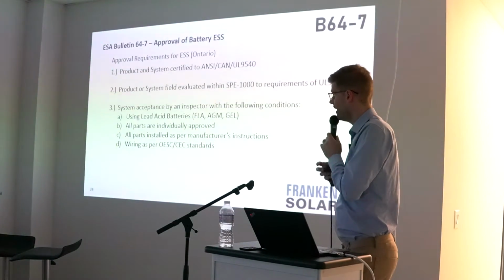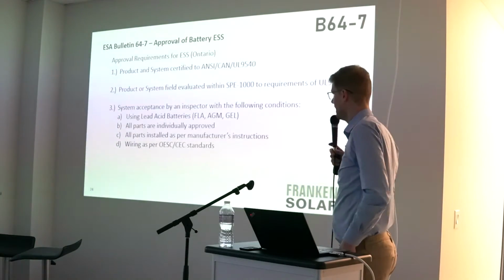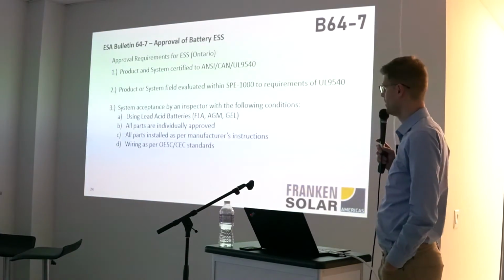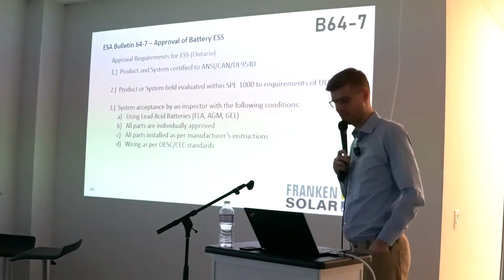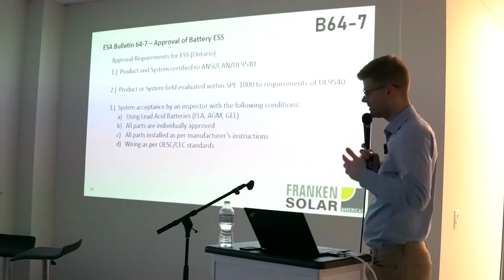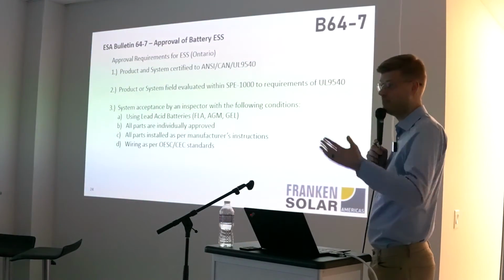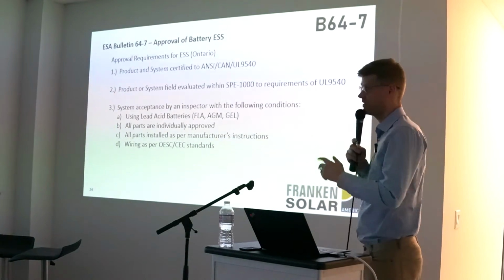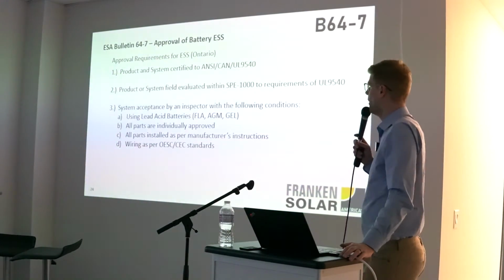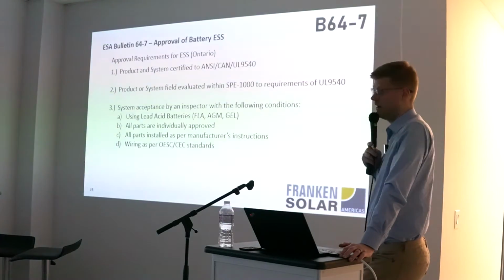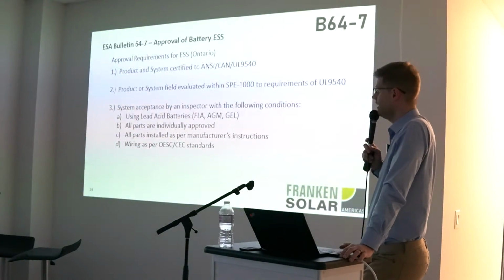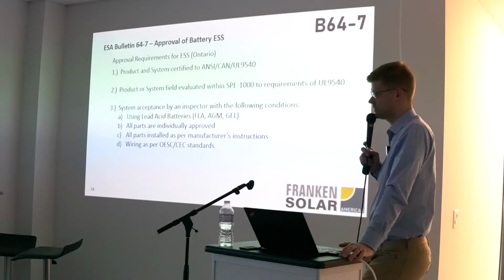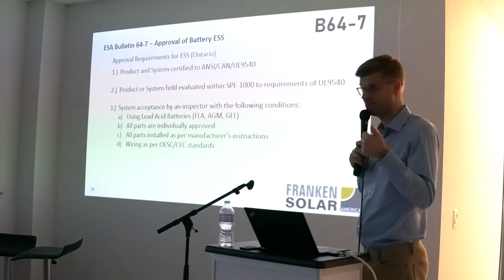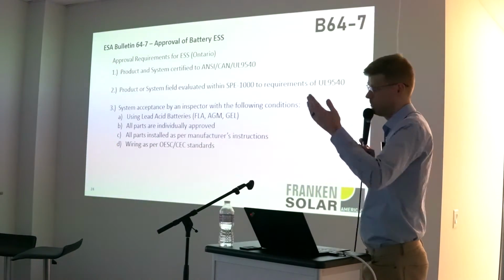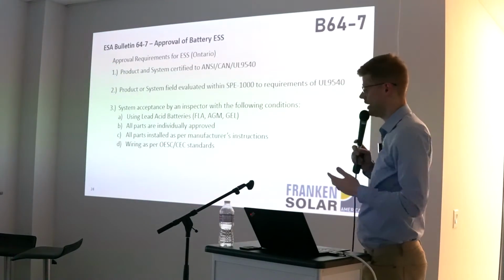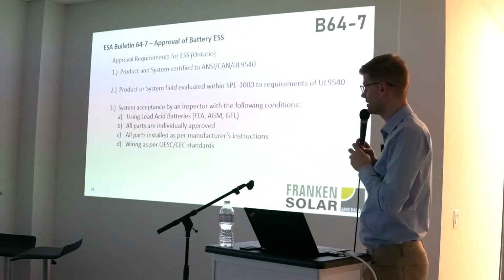And then we have another option that specifically applies to lead-acid batteries, an exemption that helps for legacy systems or very small systems or even backup systems that are still based on, for example, flooded lead-acid batteries. You can get an acceptance by your ESA inspector if your system meets the following conditions. You have to have lead-acid batteries. They can be, for example, the most common one is flooded, as I said, or a gel, so a sealed battery, for battery backup systems.